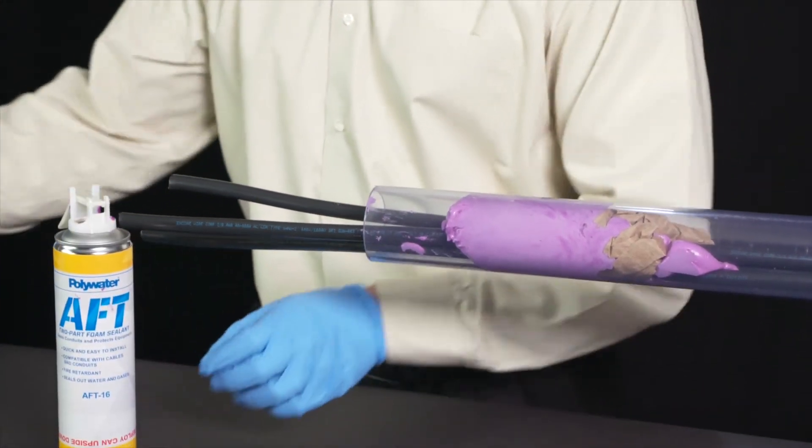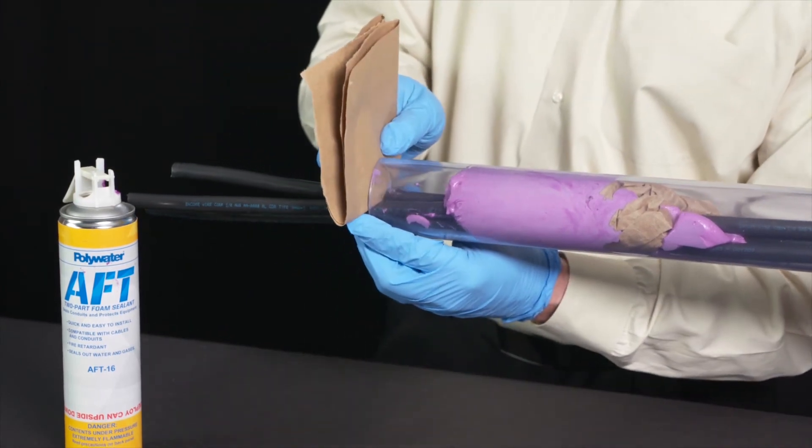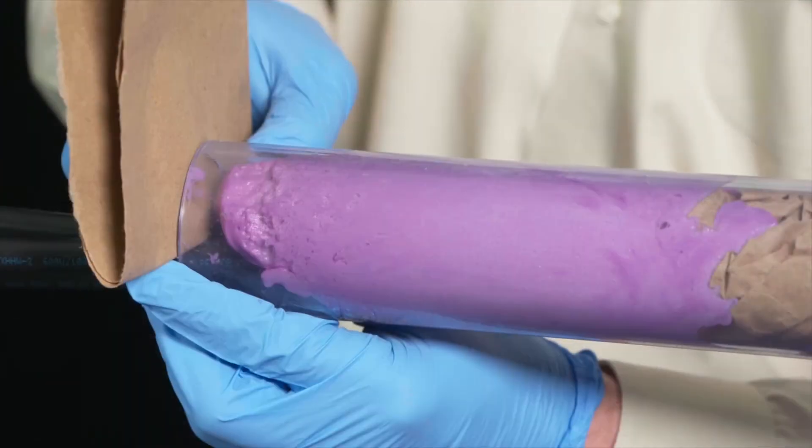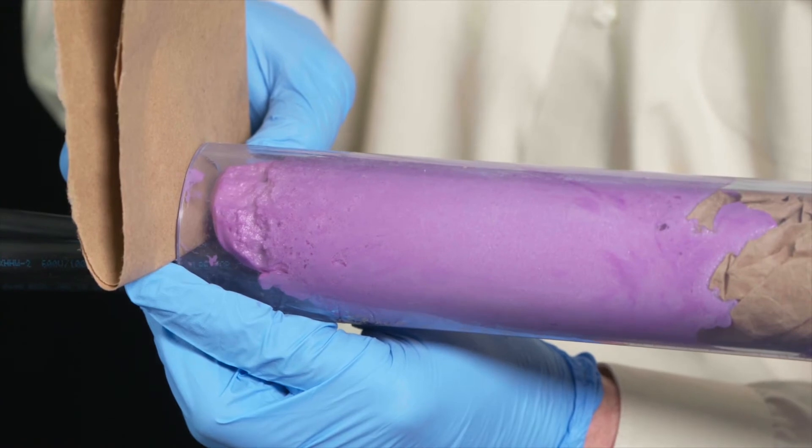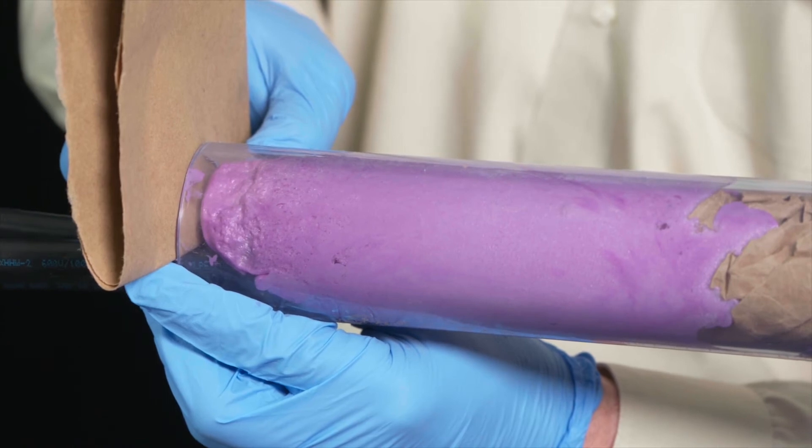After AFT has been deployed, place an additional dam on the outside of the conduit or hold with gloved hands until expansion is complete to prevent the expanding foam from escaping the conduit. The foam should be uniform in color.